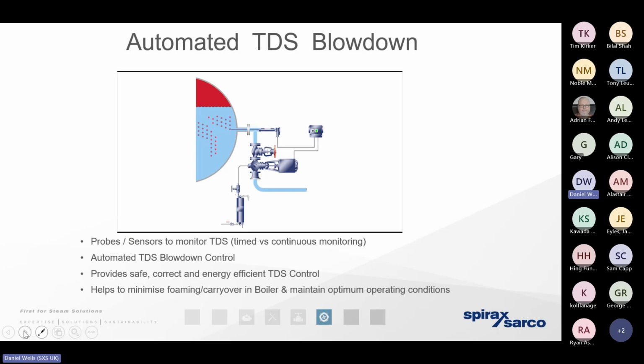So wherever possible, we want to ensure that we're monitoring the concentration of the TDS within the boiler constantly. It needs to be automated. So by having an automated TDS conductivity probe sending a signal to the modulating valve, we can bleed out the required mass of hot water to waste and no more. If we're blowing down too much, we've got a very large inefficiency, but if we're not blowing down enough, we're going to get contaminated steam. So as with the bottom blowdown, if we automate that, and if we automate the TDS blowdown, it's vitally important to make sure that it's routinely serviced and calibrated so those values don't drift.